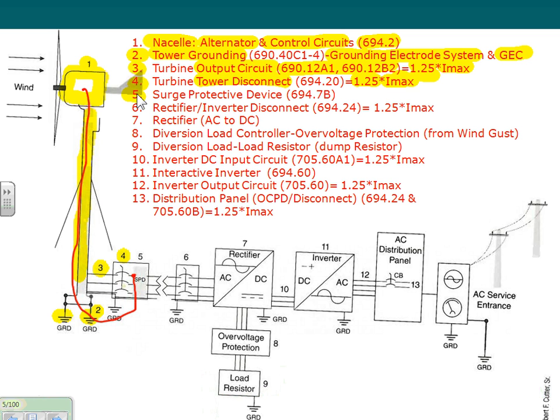The second important thing is surge protective devices. For those of us who are electricians, this is not required by the code in 2011. I can't recall any place that requires a surge protective device in the code. In 2014, there's a proposal to require it on every service, other than dwelling. My understanding is this proposal went through and will be going out for comments shortly. But they will require surge protective devices in every service for any building other than dwelling.